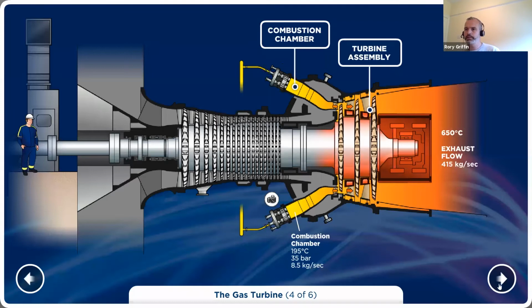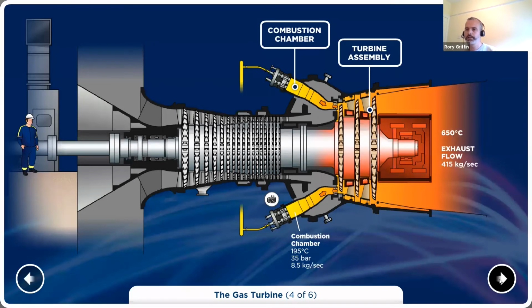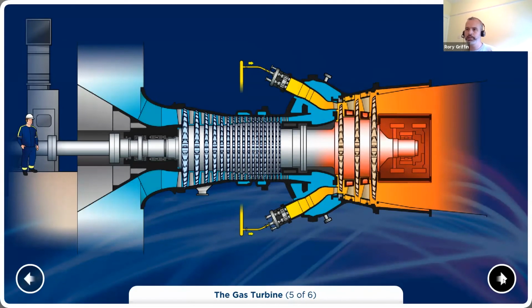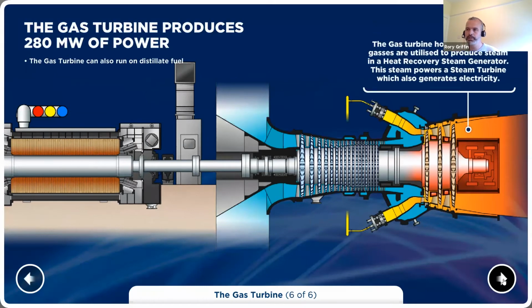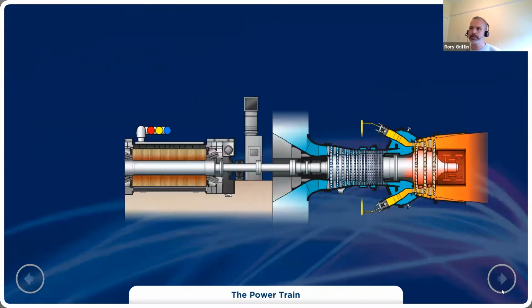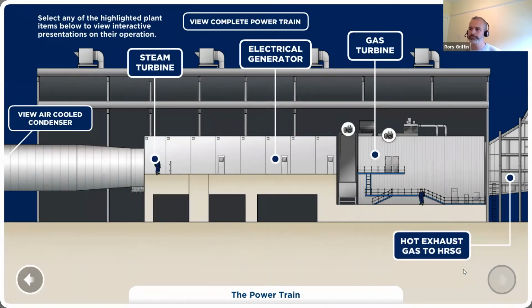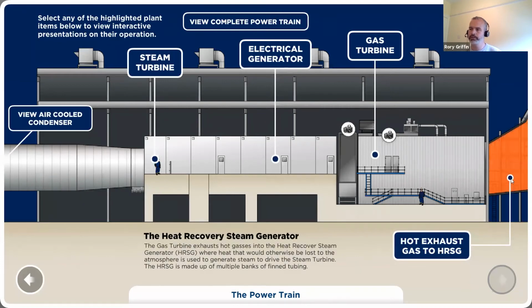Now, back in older generations of machines, if you had an open cycle gas turbine, a lot of this energy would have just gone up the stack. But what gives a unit like Whitegate and the other CCGTs in Ireland the efficiency gain is this heat is going to be used in the boiler, which we'll discuss next, to convert water to steam, and then we'll bring the steam to the steam turbine. So we'll just move to the HRSG next.